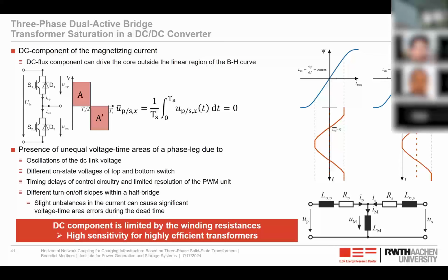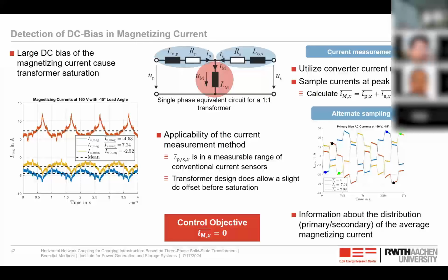However, this DC component of the magnetizing current is only limited by the winding resistances. And if we have a highly efficient transformer, typically our winding resistance is in the range of milliohms, and then we only require a few millivolts unbalanced, and then we can have quite high DC offsets occurring. So here on the left side, you see a measurement of the transformer, which is then in saturation. We first initially see the different DC offsets of the magnetizing currents, and then at some point we reach some kind of threshold value, and then really the magnetizing inductance decreases, and thus the current increases rapidly.